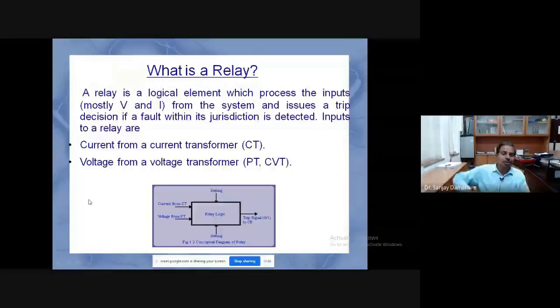We know that the relay takes a decision on abnormal conditions from the CTs and PTs, and this relay is nothing but a logic device. It has some setting, some small program. Now these CTs and PTs are something similar to the ears and eyes of the power system, of the protection system.